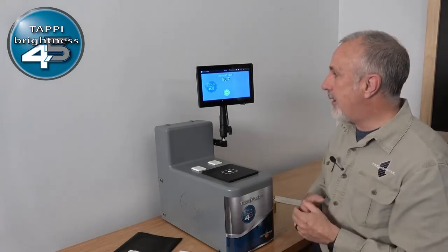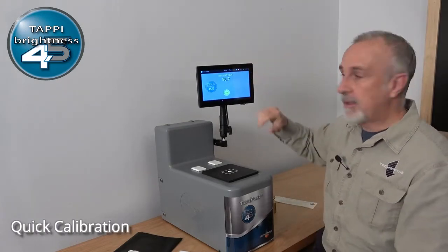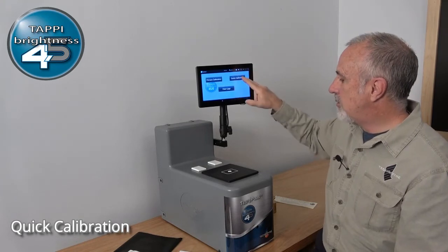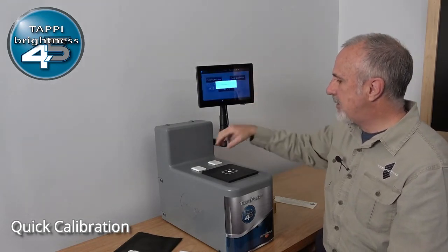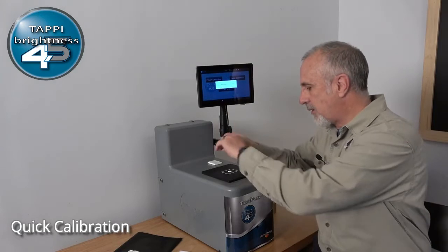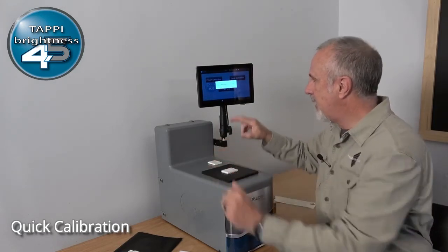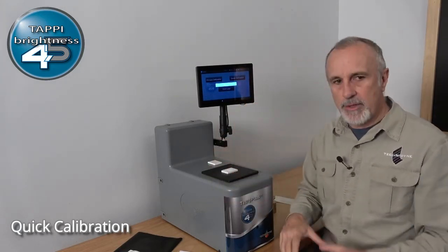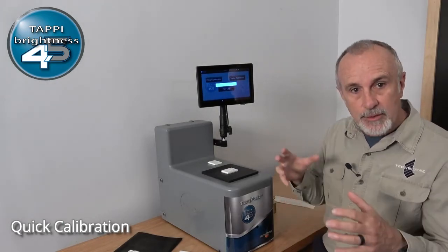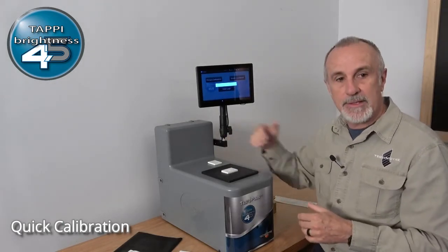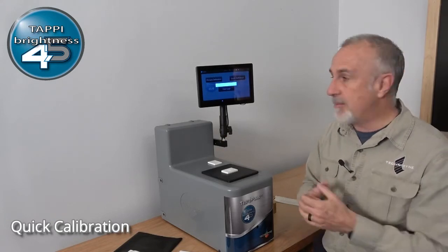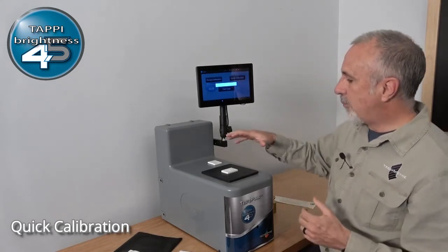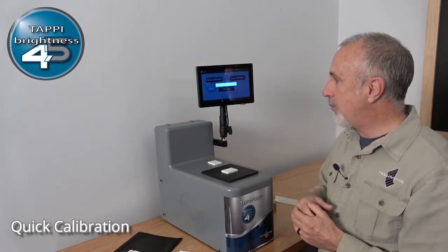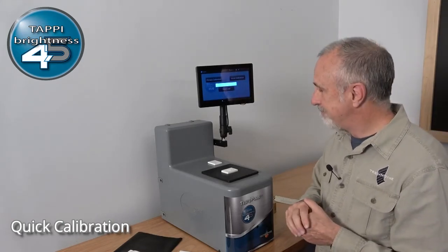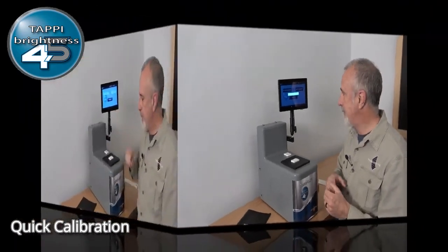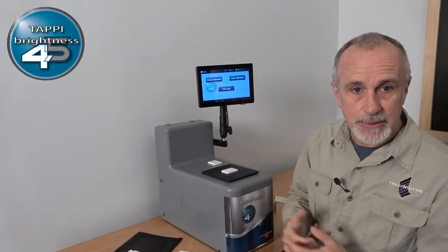If I want to do a quick cal, I go back to the calibration page. I choose the quick calibration. It tells me to insert the working standard because it has the value stored for that. I do that, click OK. And what it's going to do is force the instrument back into agreement with the value that was assigned to that when we did this primary calibration just a minute ago. Once it completes that step, the calibration sequence will be completed for the quick calibration, and we'll be ready to test again. So the calibration sequence for this instrument is really quite simple.